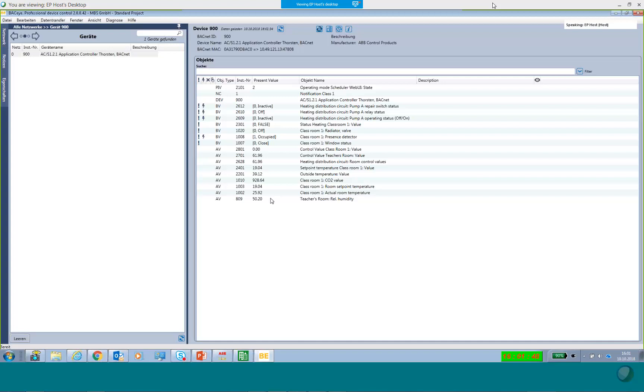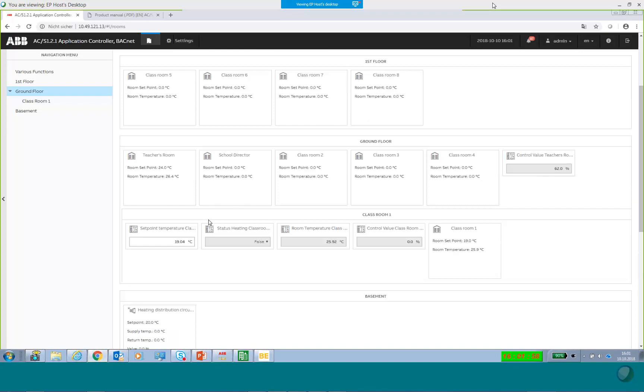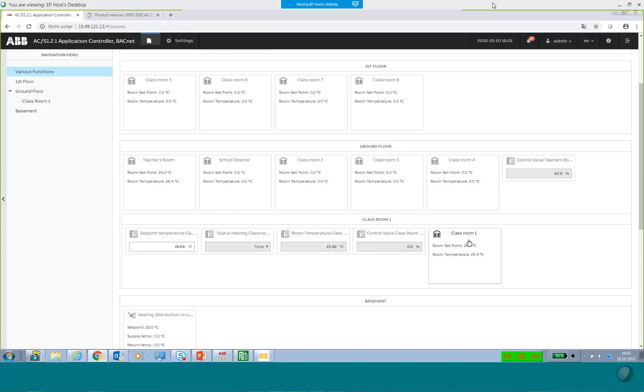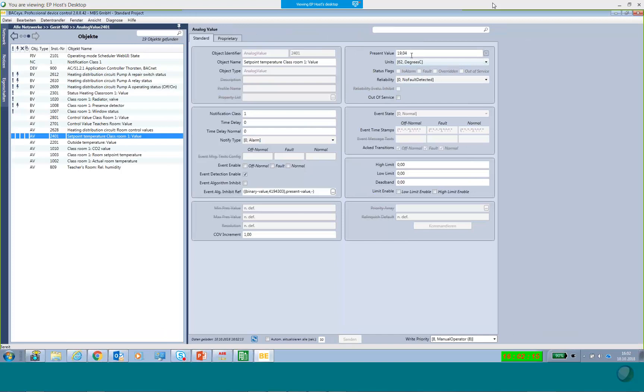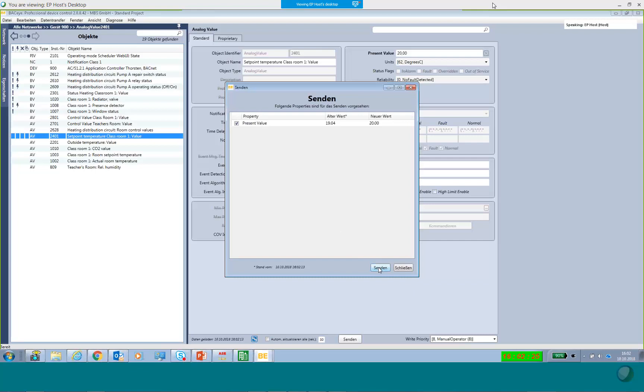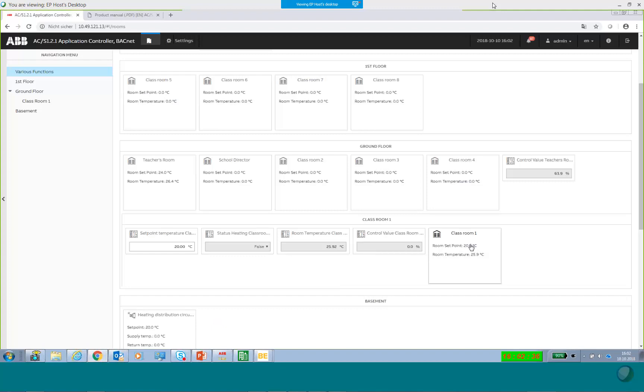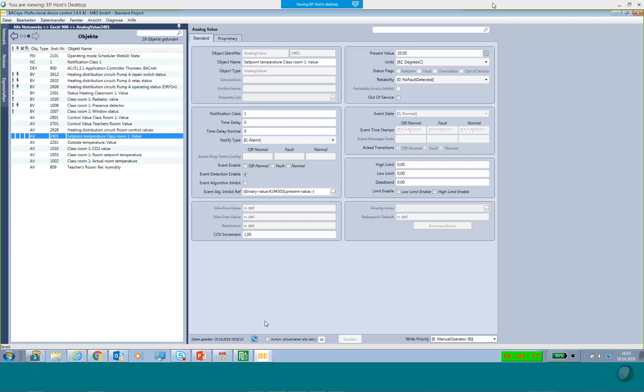I also demonstrate writing from BACnet to KNX: the classroom set point in BACeye shows 19°C, confirmed in the web UI as 19°C. Using BACeye I change the value to 20°C and send it from BACnet. The web user interface immediately updates to show the room set point as 20°C. This demonstrates complete bidirectional communication: KNX → application controller → BACnet, and BACnet → application controller → KNX and web UI. It is very simple to assign a data point to BACnet and then it becomes available.